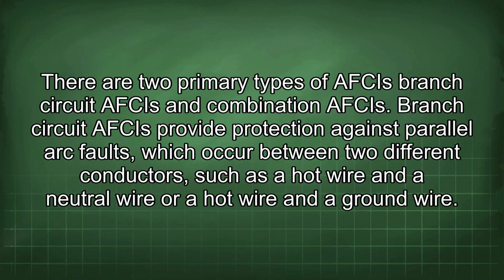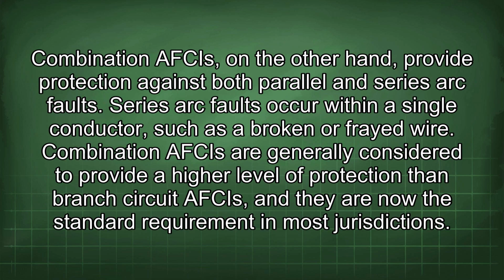There are two primary types of AFCIs: branch circuit AFCIs and combination AFCIs. Branch circuit AFCIs provide protection against parallel arc faults, which occur between two different conductors, such as a hot wire and a neutral wire, or a hot wire and a ground wire. Combination AFCIs, on the other hand, provide protection against both parallel and series arc faults. Series arc faults occur within a single conductor, such as a broken or frayed wire. Combination AFCIs are generally considered to provide a higher level of protection than branch circuit AFCIs, and they are now the standard requirement in most jurisdictions.